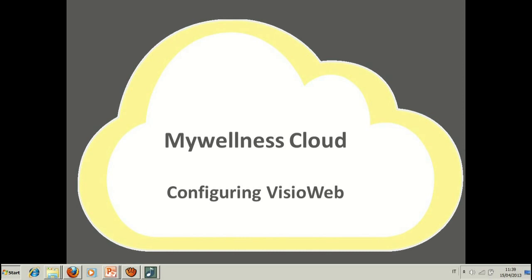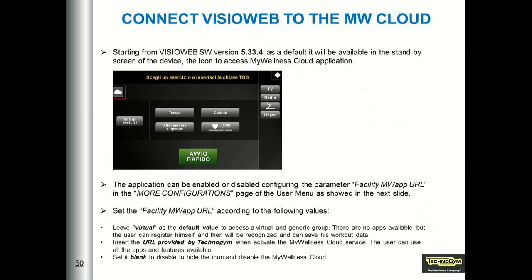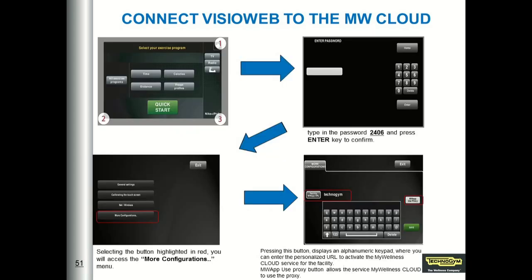Another hardware component of MyWellnessCloud is VisioWeb. Starting from version 5.33.4, VisioWeb can be connected to MyWellnessCloud — you can see this because in the standby screen there is an icon with a cloud. To connect VisioWeb to the cloud, very similar to what we have seen with VisioSelf, VisioWeb needs to be connected to the network, the facility URL needs to be inserted into its configuration, and also for VisioWeb we need to set time and timezone. For connecting VisioWeb to the network, you can follow the same procedure seen for VisioSelf, because the menus are exactly the same.